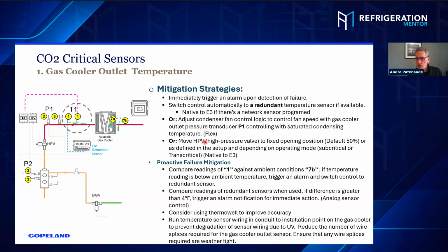We can move the high pressure valve to a fixed opening position. It defaults to 50%. It's native to the E3 setup, but just because it defaults to 50% doesn't mean you have to leave it at 50%. If you know that when you're operating, that valve is normally operating at 25% because it might have been oversized to begin with, then if it defaults to 50%, it'll be way too much. Yeah, so you got to think about those things, even though there's a default.